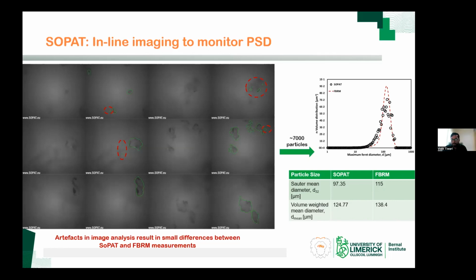than what you would usually encounter in industrial crystallization processes. The suspension was under similar stirring conditions to those in our stirred tank crystallization experiments. We immersed an FBRM probe and a SOPAT probe in the same suspension and measured the particle size distribution using both techniques, and got fairly similar PSDs. The slightly smaller value of the mean diameter for the SOPAT compared to FBRM could be because of the small artifacts that we see in some of the pictures over here. So I've circled some of those artifacts.